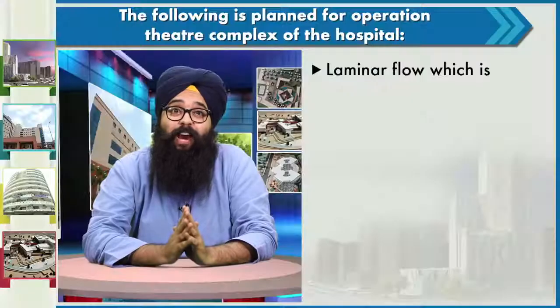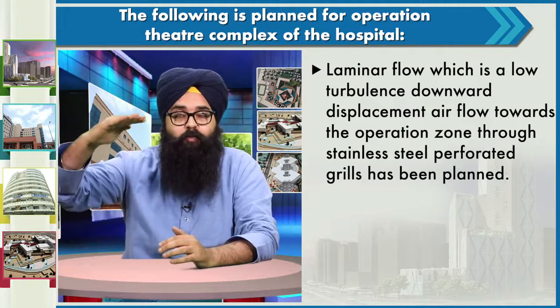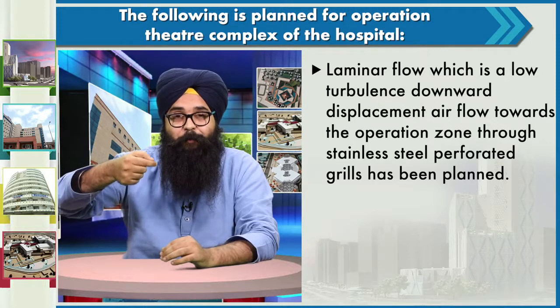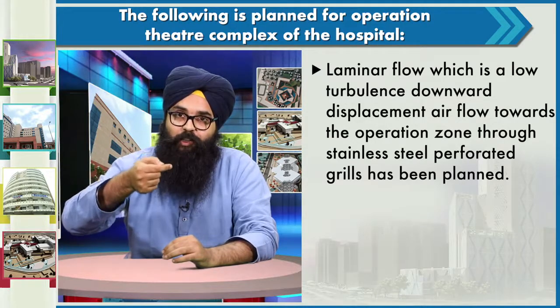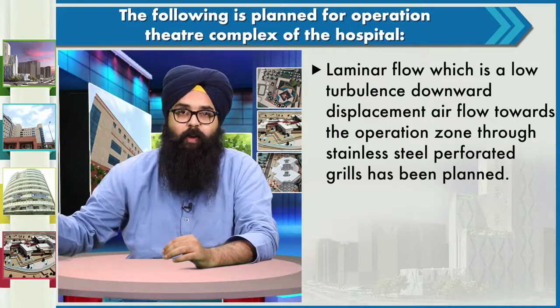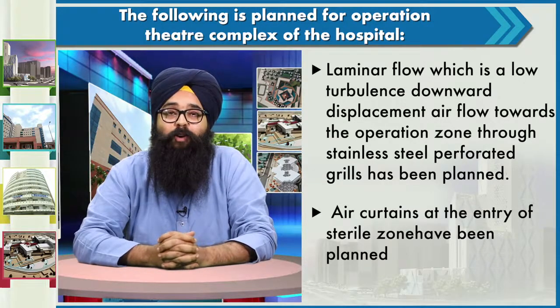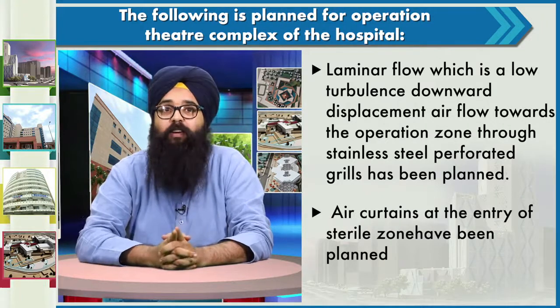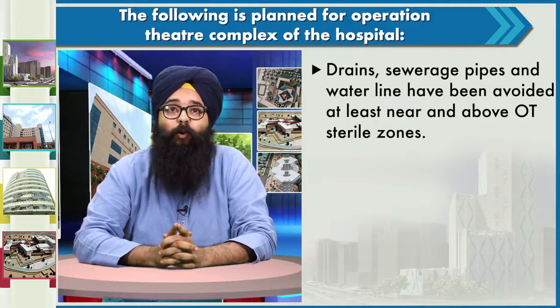An important factor is the HVAC design for an operation theatre. OT HVAC design is unique because it uses laminar flow — a low-turbulence downward displacement of airflow. Air flows from the top downward, first touching the healthcare provider then the patient, then exiting below where it is sucked back into the system and passed through the AHU filters. Air curtains at the entry of the sterile zone must be planned. Drains, sewerage pipes, and water lines should be avoided near and above the OT sterile zones.